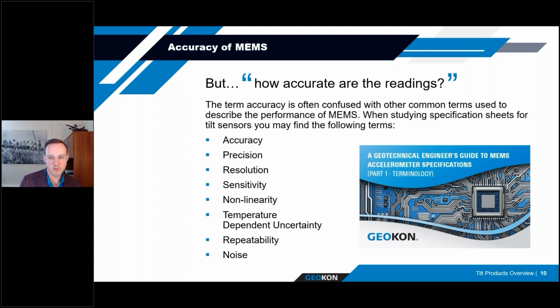So these are some of the terms that we typically come across when talking about the kind of generalized term of accuracy, right? So we have terms like precision, resolution, sensitivity, nonlinearity, temperature dependent uncertainty, repeatability, and sensor noise. And these different terms are sometimes used interchangeably and in some cases incorrectly. So it's important to understand what each of these terms means and how the value that's on the manufacturer specification sheet will impact the quality of data that you get on your specific application.